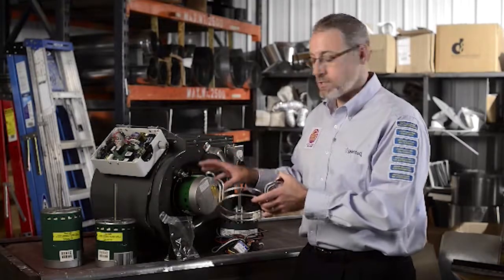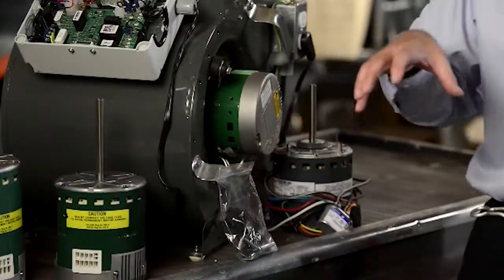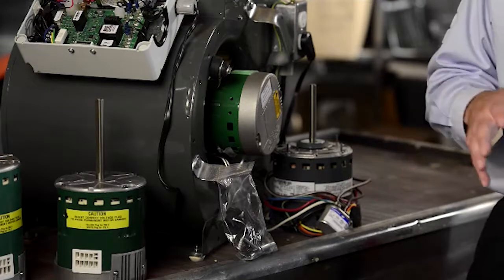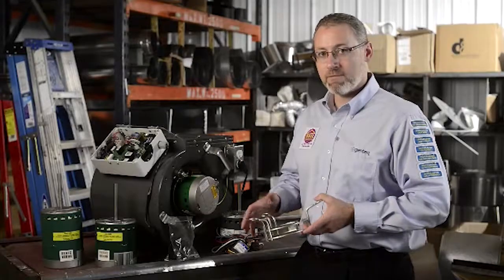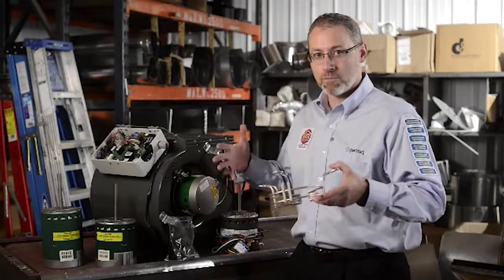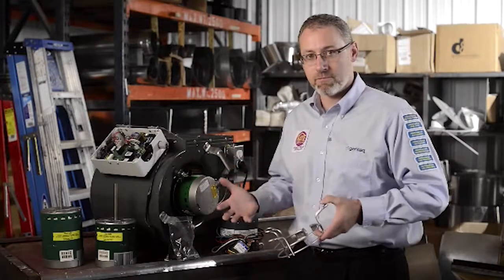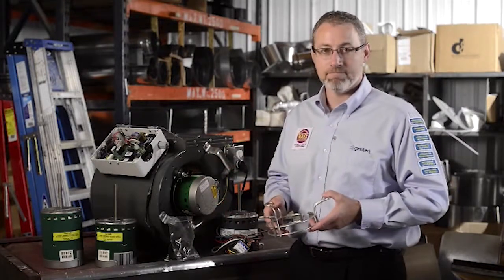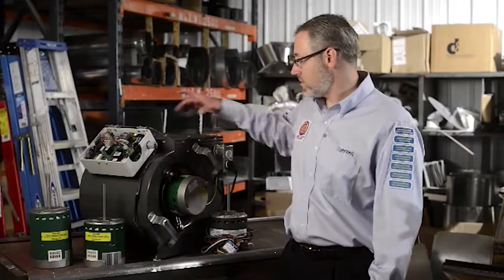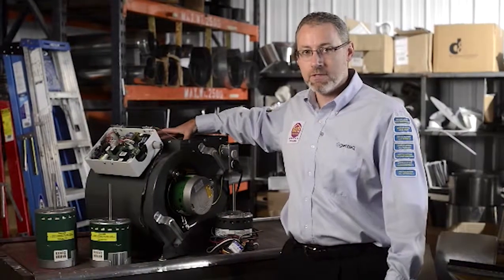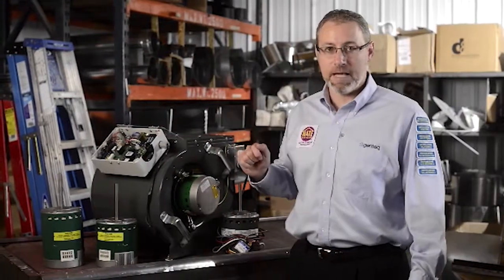We want it to exist so that the connectors are facing down or between the 4 and 8 o'clock position. That way, if any water gets on the motor shell or the motor harness, it rolls off instead of running into the electrical connections. And last but not least, our industry best practices tell us to center the blower wheel in the housing and then tighten the hub bolt on the flat part of the shaft.